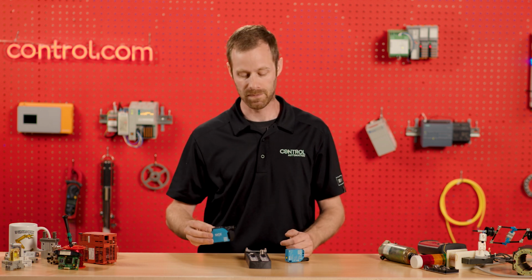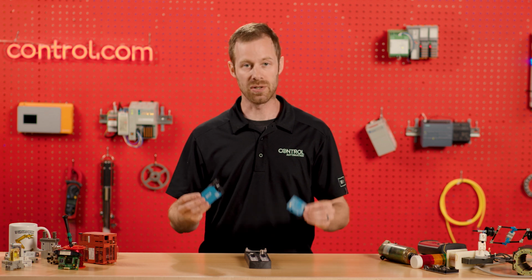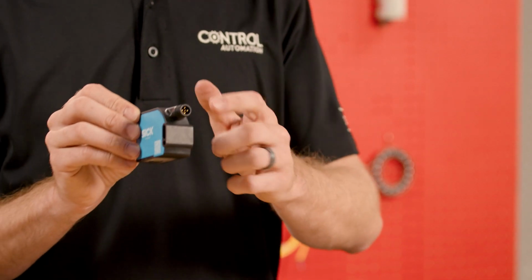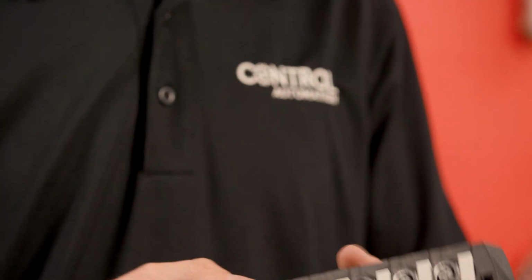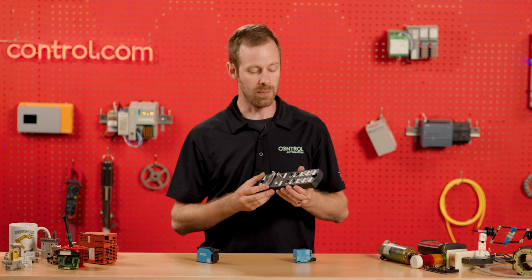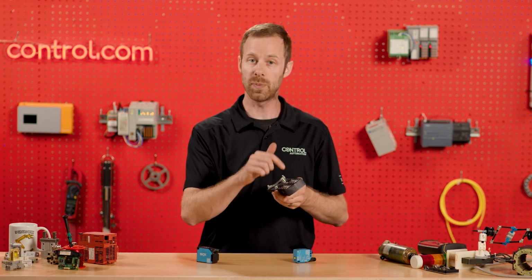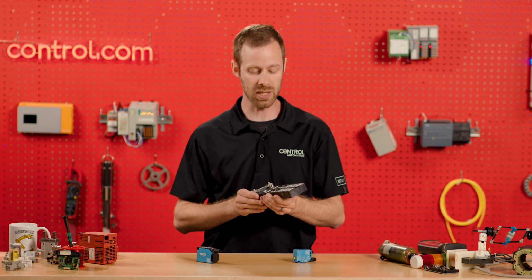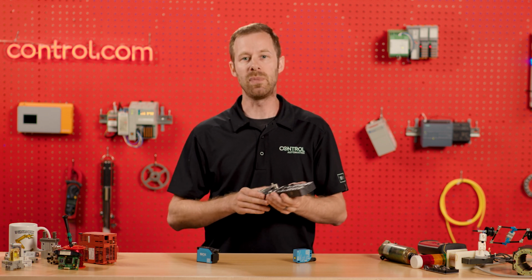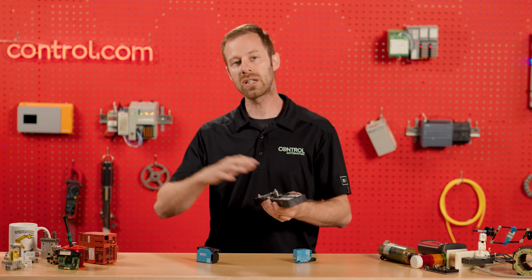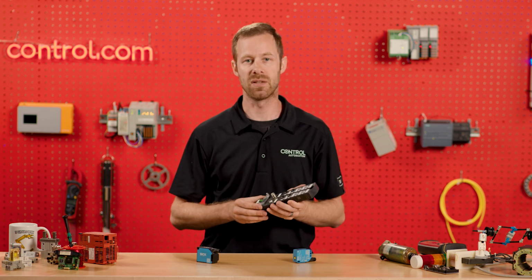It's not only the sensors, the field devices themselves, that are necessary for I/O Link, but the connectors, which normally use the standard M12 connectors, go back to an I/O Link hub or a master device. An I/O Link hub allows input of multiple I/O Link and also discrete devices, so you can still use your old discrete devices, but they can also then be distributed back to a network like Ethernet or Profinet to communicate back to our PLC system.